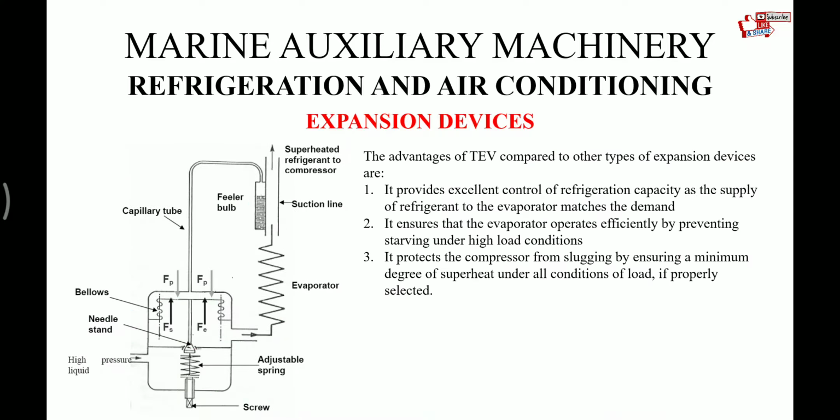Now let's see the advantages of this expansion valve. It provides excellent control of refrigerant capacity, as the supply of the refrigerant to the evaporator matches the demand. It ensures that the evaporator operates efficiently by preventing starving under high load conditions. It protects the compressor from slugging by ensuring a minimum degree of superheat under all conditions of load.